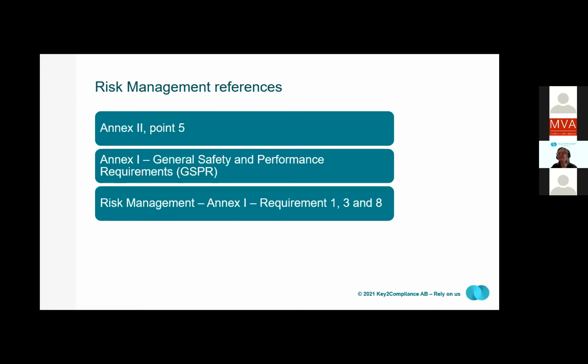So Annex 2 is the annex which describes what you need to include in your technical documentation together with the post-market surveillance information in Annex 3. The requirements you need to fulfill are listed in Annex 1, the General Safety and Performance Requirements, the GSPRs, that is replacing the essential requirements from MDD. Annex 2.5 tells you that you need to include information referred to in Annex 1, GSPR 1, 3, and 8 in your technical documentation. And those GSPRs are related to the risk management and the benefit-risk analysis.